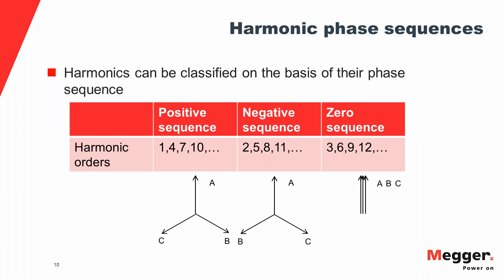Harmonics can also be classified in terms of their phase sequence. Phase sequence refers to the phase relationship between the three phases in a three-phase system. In a positive sequence system, B lags behind A by 120 degrees, and C lags behind B by 120 degrees — moving clockwise on the vector diagram. In a negative sequence system, it's the opposite: B leads A by 120 degrees, C leads B by 120 degrees, moving counterclockwise. In a zero-sequence system, there is no phase difference between the three phases — all three phases are in phase with each other.